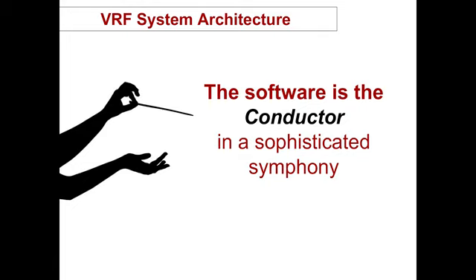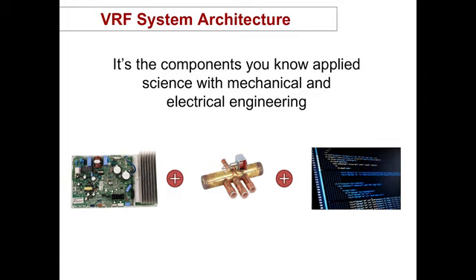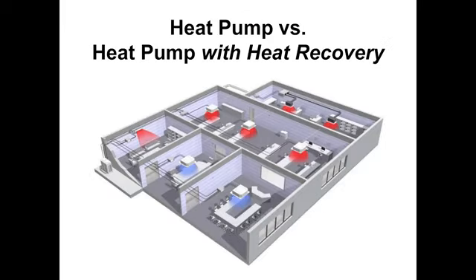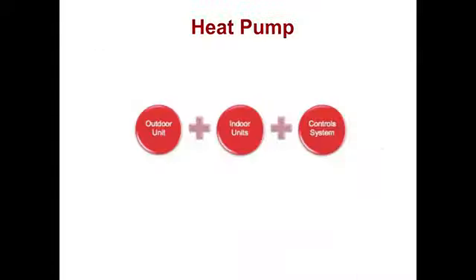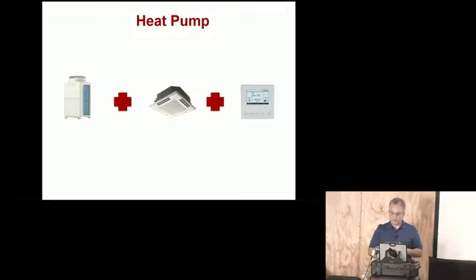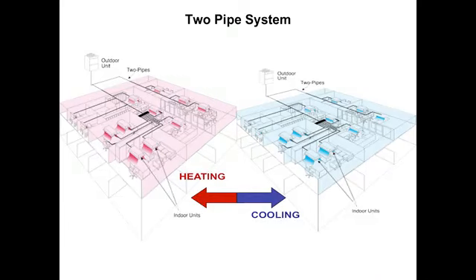Again, just to simplify it, the software is a conductor in a sophisticated symphony. There's a lot of stuff going on. It's the components, applied science, and mechanical and electrical engineering. All right, so we have heat pump, and then we have heat pump with heat recovery. So with a heat pump, you have 3 general components. You have the outdoor unit, and the indoor units, and the controls. Pretty straightforward, right? You got one mode at a time, but everybody has their own control.